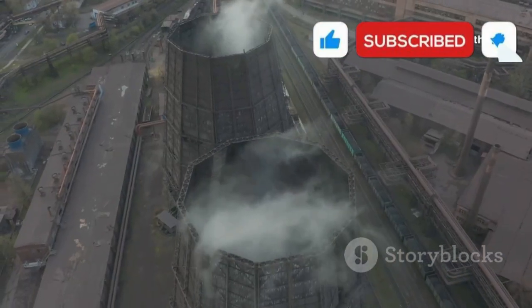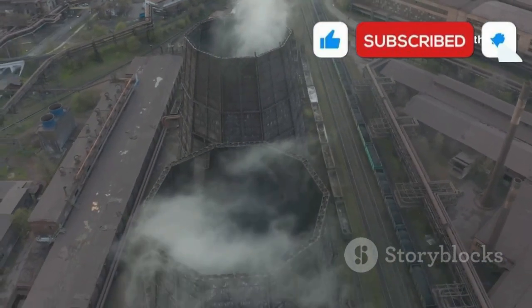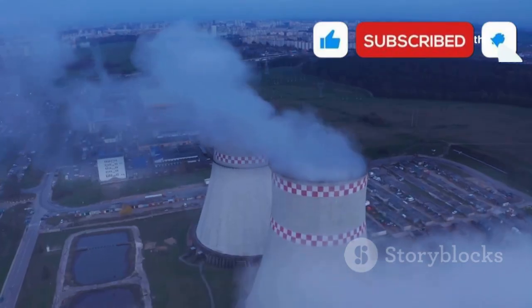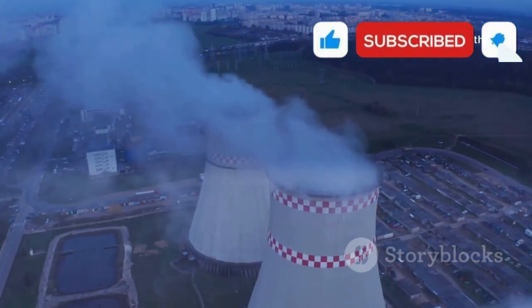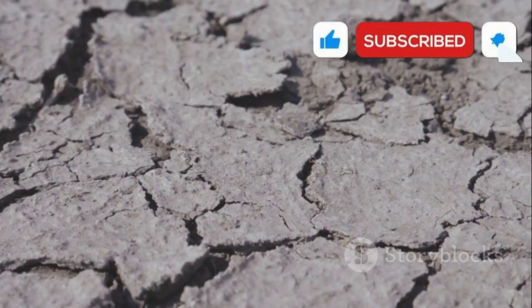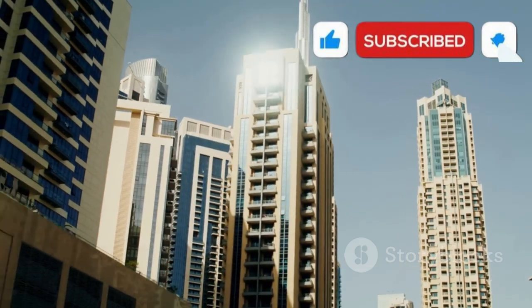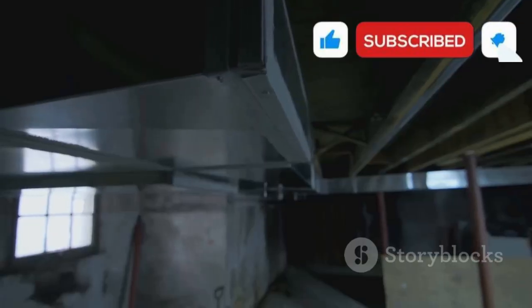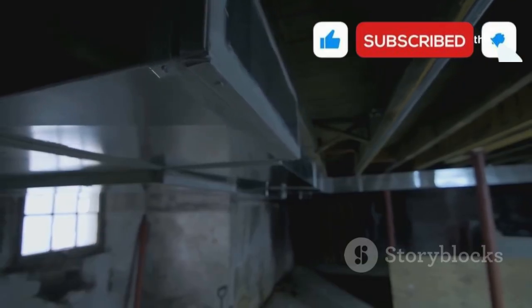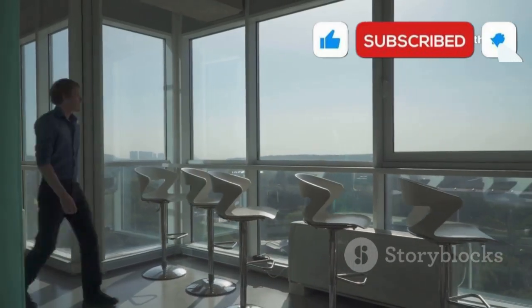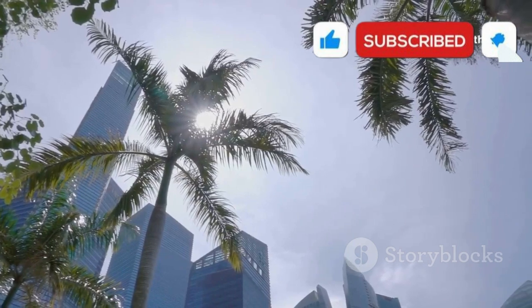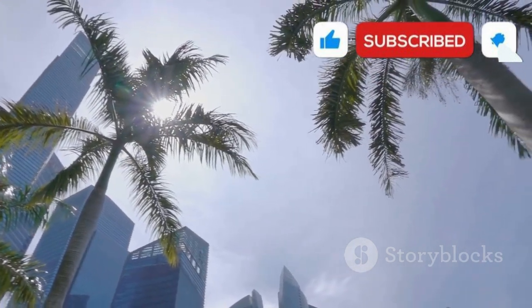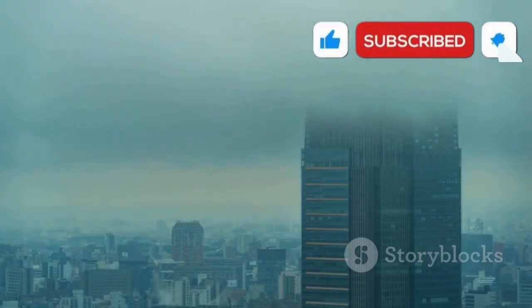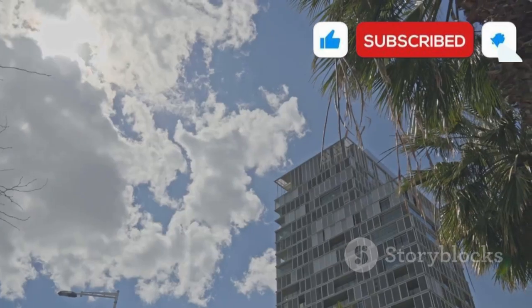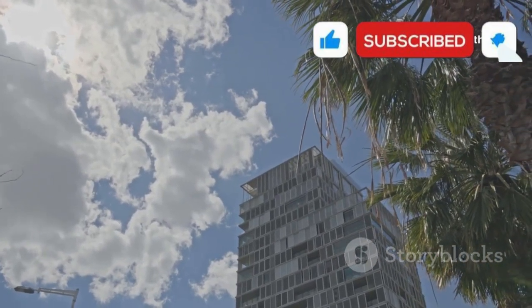Water conservation is critical. Cooling towers use a lot of water, so engineers use hybrid towers and recycle condensate to minimize waste. Every drop counts in the desert. Desert skyscrapers are marvels of engineering, balancing massive cooling needs with limited water. The result: comfortable interiors in the harshest environments. But deserts aren't the only challenge. Let's head to the tropics. There, humidity is the real enemy. Here's how skyscrapers battle heat and moisture.